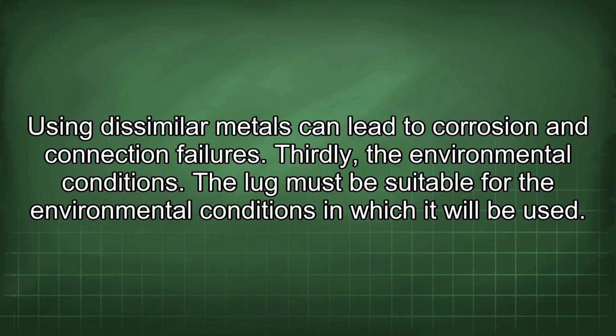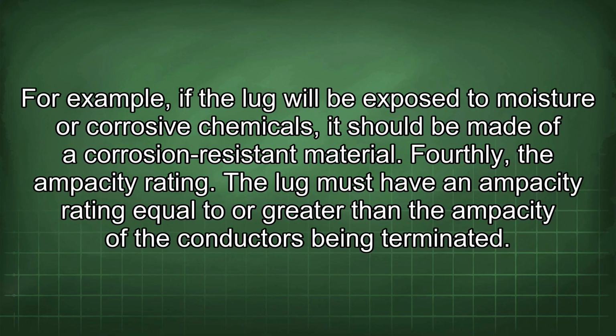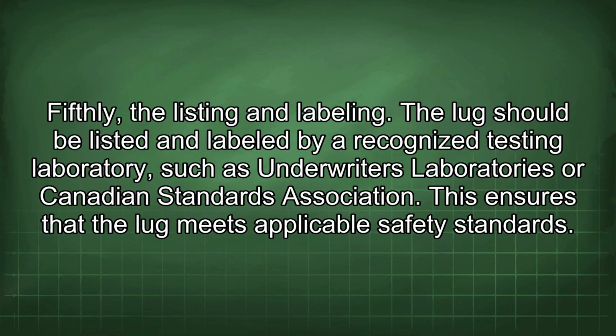Thirdly, the environmental conditions. The lug must be suitable for the environmental conditions in which it will be used. For example, if the lug will be exposed to moisture or corrosive chemicals, it should be made of a corrosion-resistant material. Fourthly, the ampacity rating. The lug must have an ampacity rating equal to or greater than the ampacity of the conductors being terminated. Fifthly, the listing and labeling. The lug should be listed and labeled by a recognized testing laboratory such as Underwriters Laboratories or Canadian Standards Association. This ensures that the lug meets applicable safety standards.